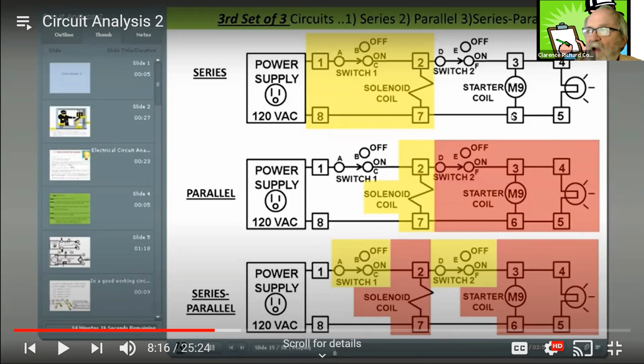And that wouldn't be right because we have a flow through right here. Terminal 6, we're going to have 0 volts there because we have 0 volts at our light, and that's got to come for the complete circuit there. So for the most part, you guys got it right. You went right for the terminals on the starter coil itself. Nice job.